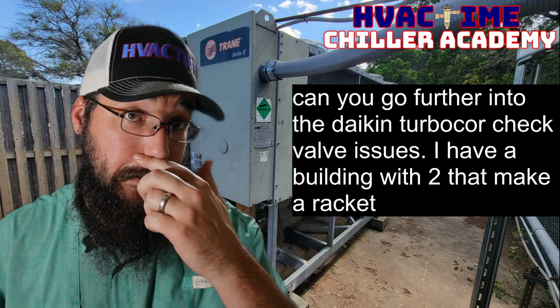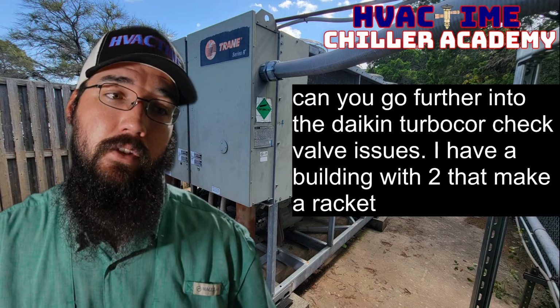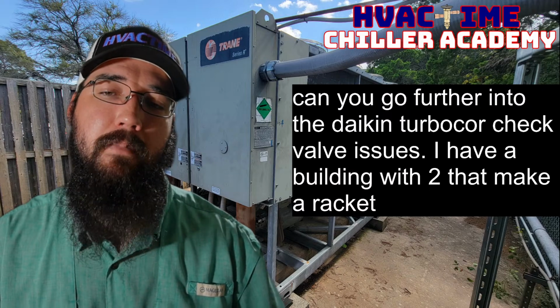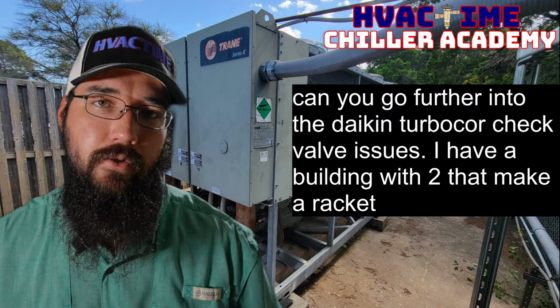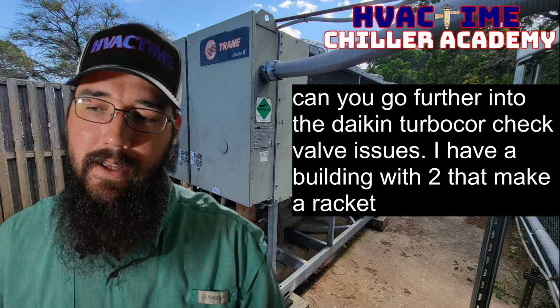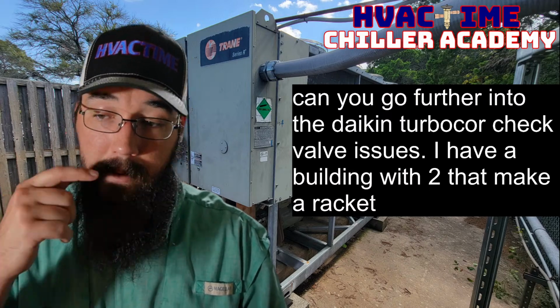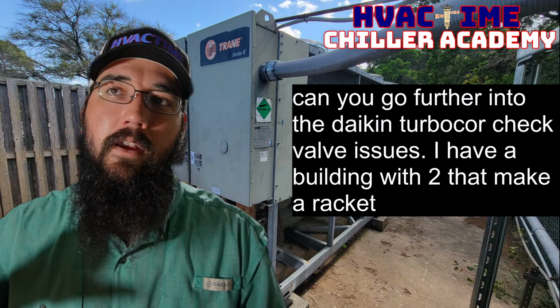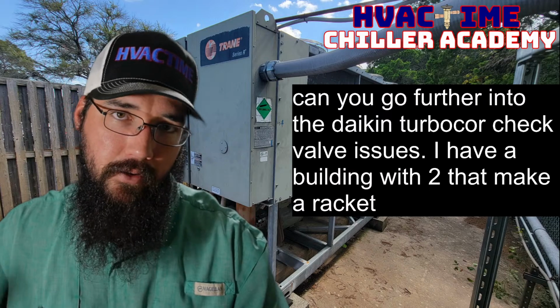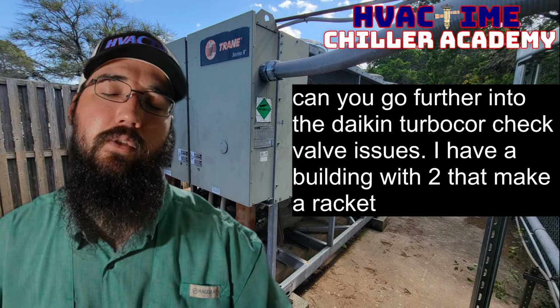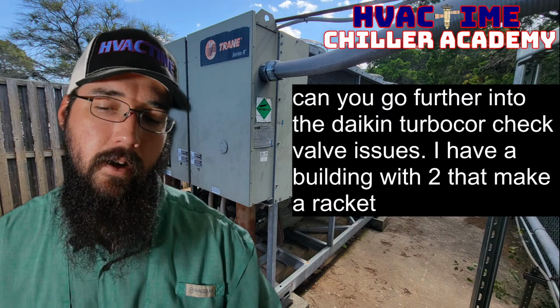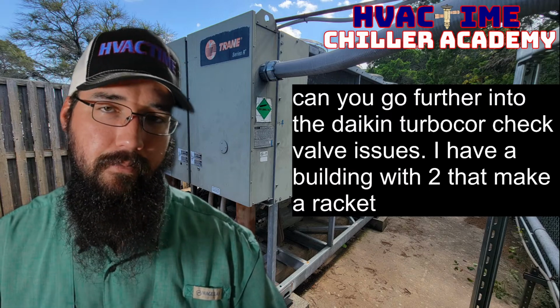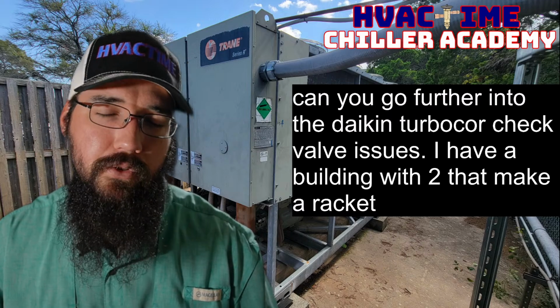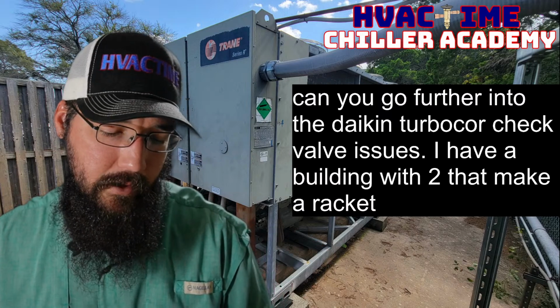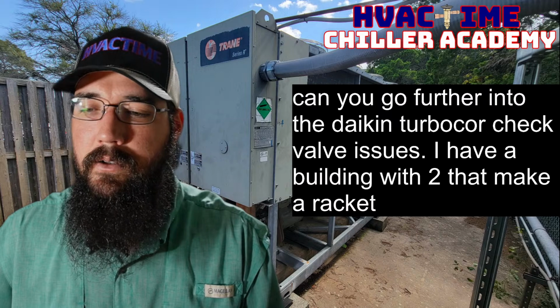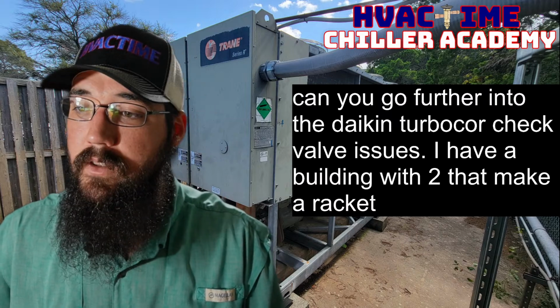At some point in this process, you're probably just going to have to get Daikin involved and get their input on what you have and what kit you're going to need to correct this, because they've had to address it. This was a major issue for them for a lot of years when they were first getting these machines out into the market. Jason made a comment too, you will need to update the software when installing that valve, because obviously that wasn't part of the original software and scope when they first built them. So if you do the upgrade package, you'll need to update the firmware, which on the Pico 2 series isn't that complicated, but isn't the most straightforward thing either. It could be more intuitive in my opinion, but they're still using the Pico 2 controllers in those systems.